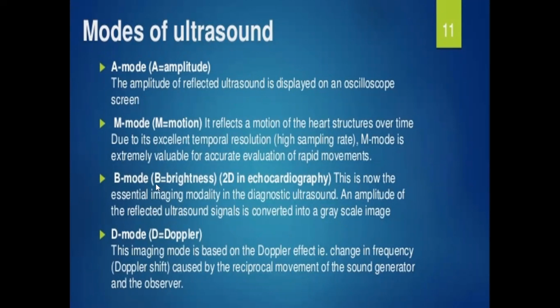Then we have your B mode, brightness mode, 2D in echocardiography. This is now the essential imaging modality in diagnostic ultrasound. The amplitude of the reflected ultrasound signal is converted into a grayscale image. So this is the one we use. Whatever the mode, the bounced waves come back to the CPU as multiple dots, converted into one processor and displayed as a grayscale image. If it's nearer, it appears brighter. If it's deeper, it appears darker.